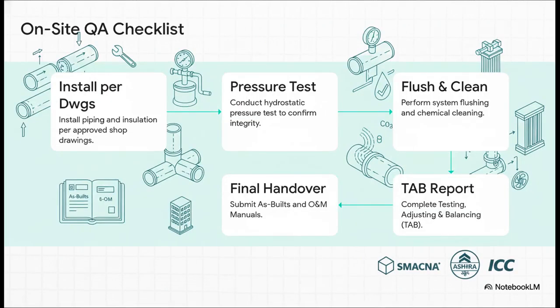And to make sure none of those mistakes happen, here is your on-site checklist for success. Every single one of these steps, from the hydrostatic pressure test that proves the pipes won't leak, to the final TAB report that verifies you have the right water flow everywhere, each one is a mandatory checkpoint. They're directly linked to codes from SMACNA, ASHRAE, and others. You follow the list, you stay out of trouble.